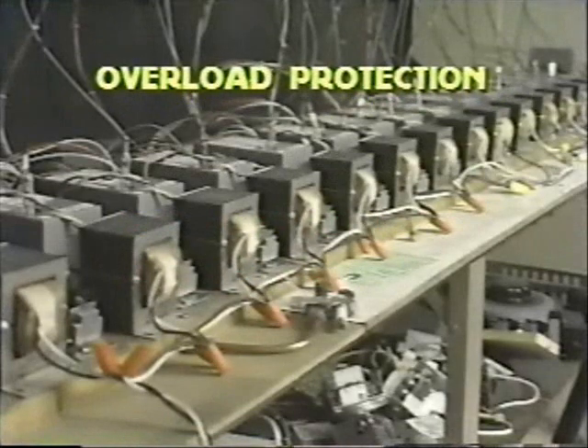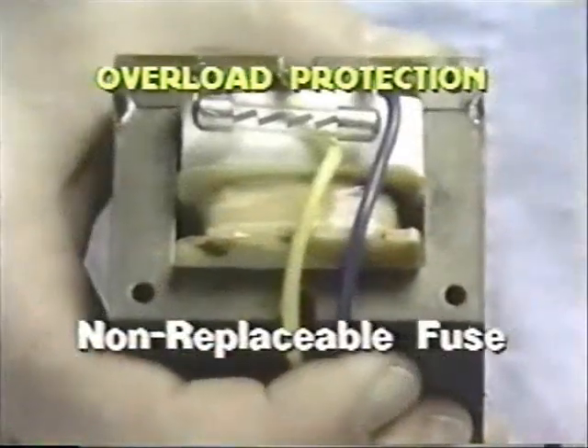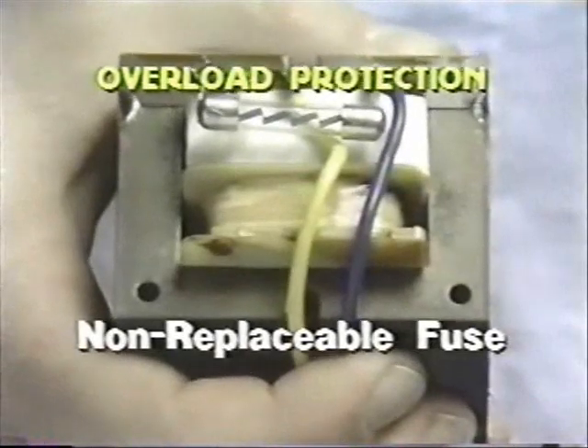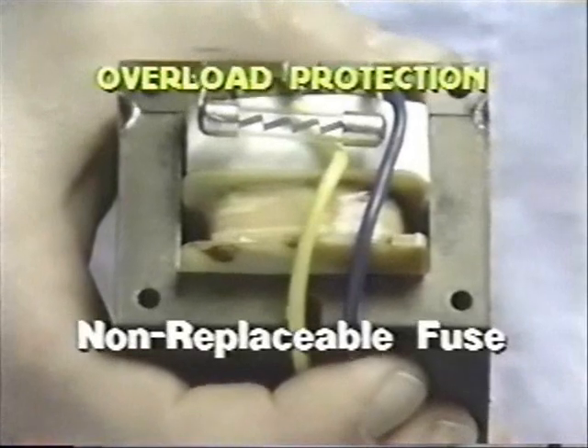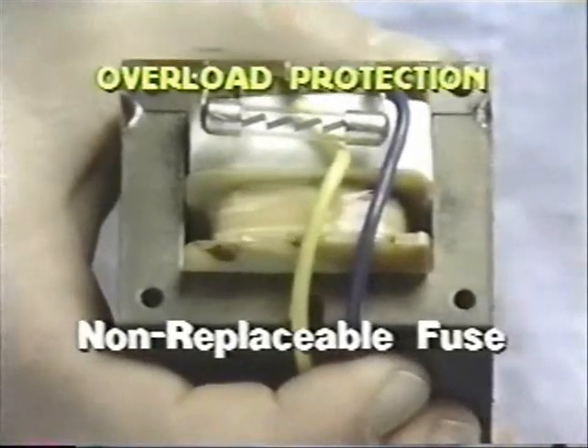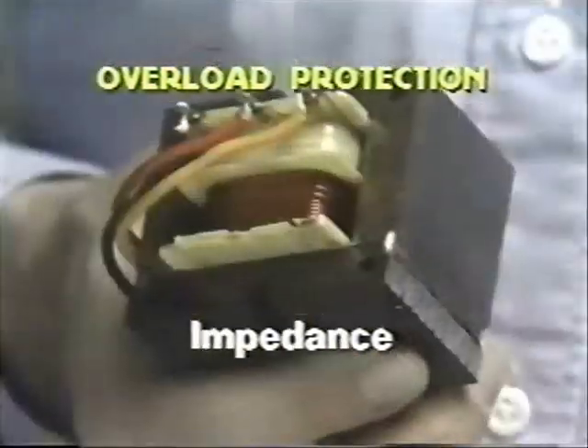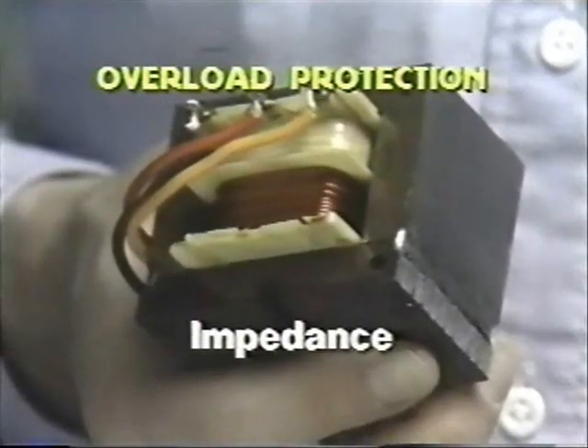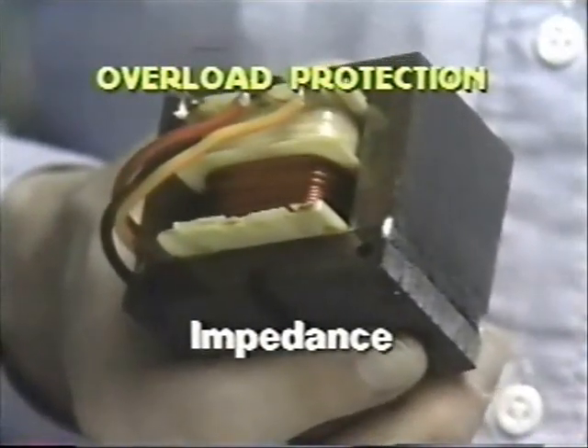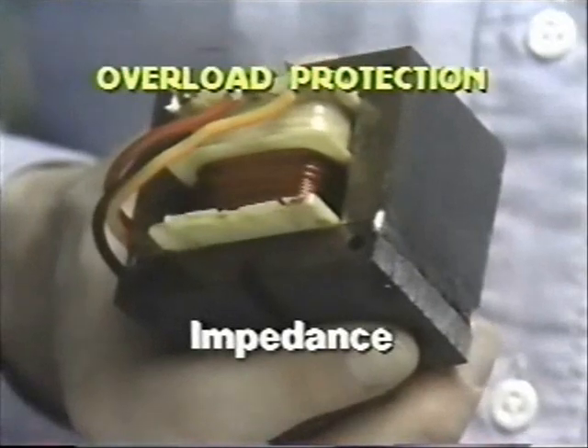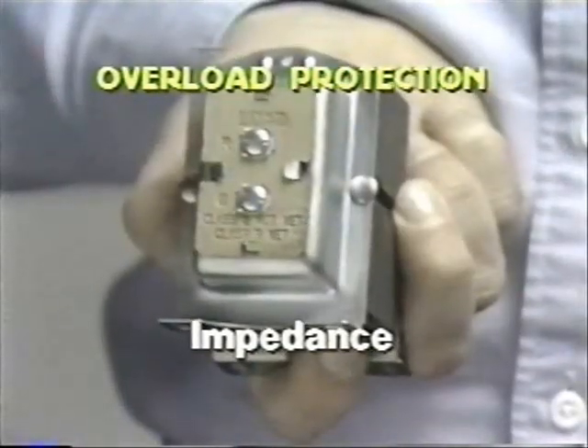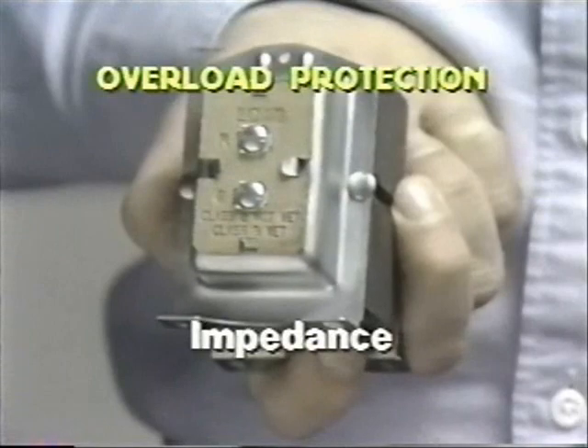Different types of overload protection may be used in Class 2 transformers to meet UL safety standards and the NEC code. One type uses a non-replaceable fuse that opens to prevent excess current flow. The fuse may be activated by either heat or current and may be located in either the primary or secondary winding. Other transformers are designed with enough impedance to prevent overheating, so they don't need fuses. In such transformers, voltage drops off very rapidly when there's an overload.